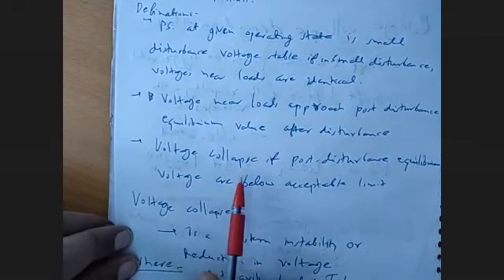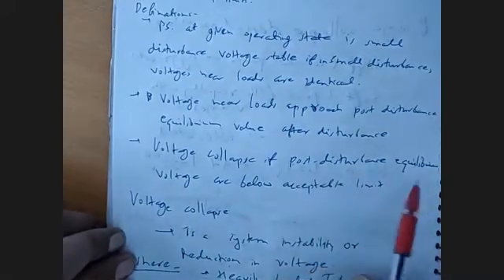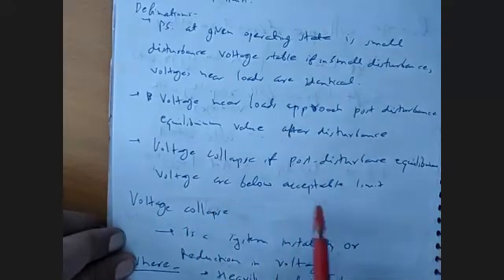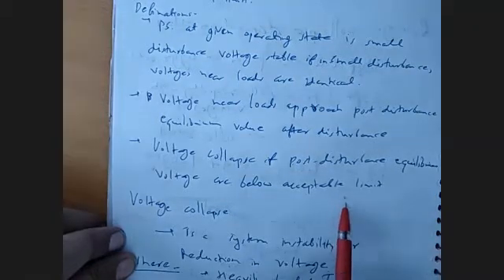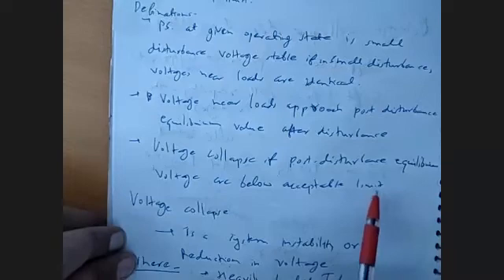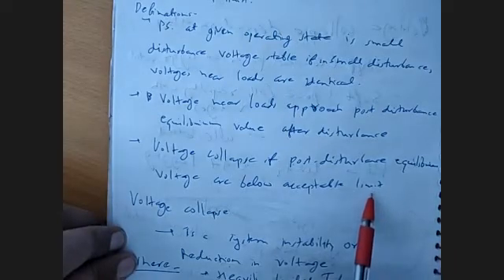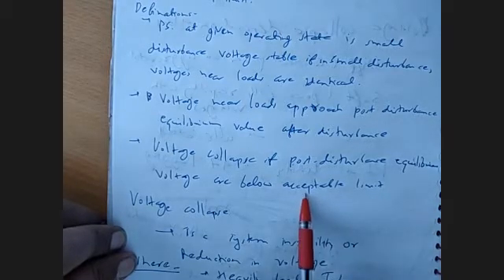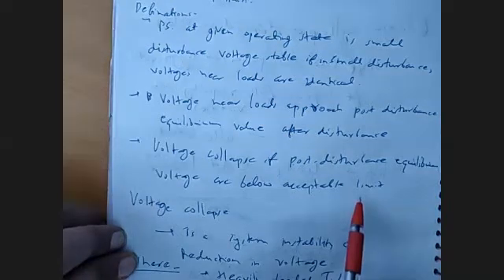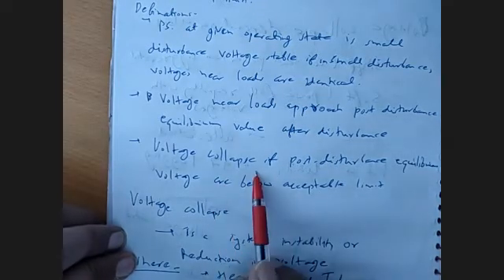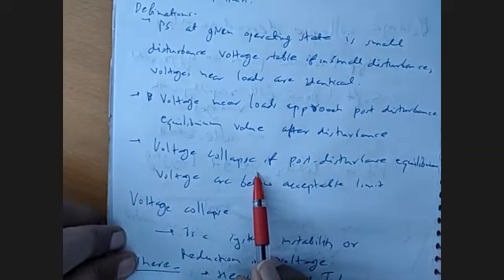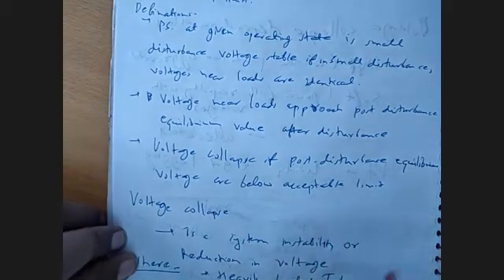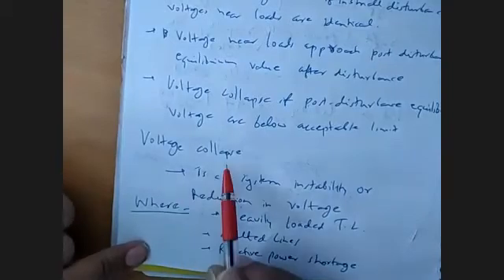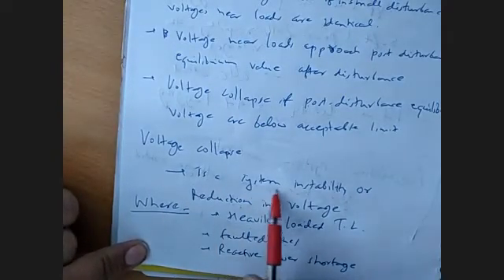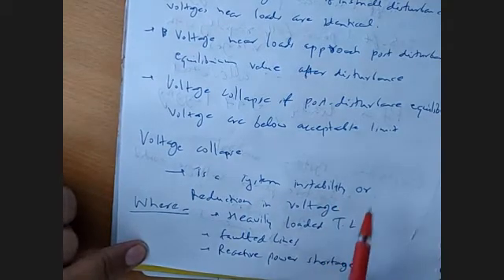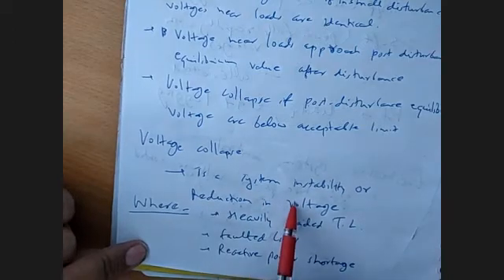Next is the voltage collapse. If the post-disturbance equilibrium voltages are below the acceptable limit, that means the system is not able to regain the previous value of voltages and the voltages are not within the accepted limit, then that is known as a voltage collapse. That means that the system has collapsed and the voltage is now not in the acceptable range of the system. So voltage collapse indicates a system instability, or it indicates the reduction in the voltages in the system.